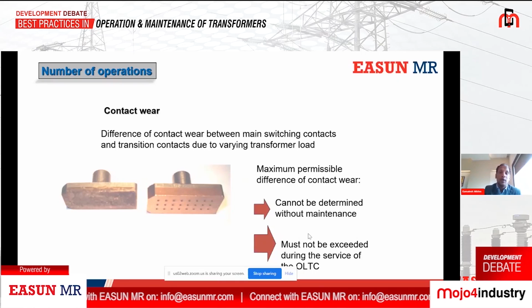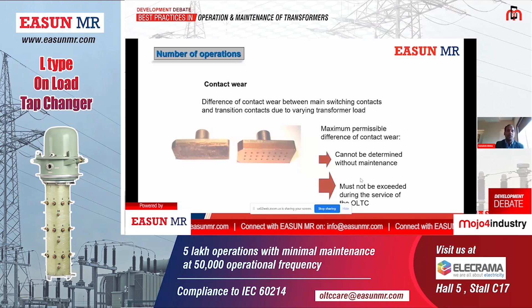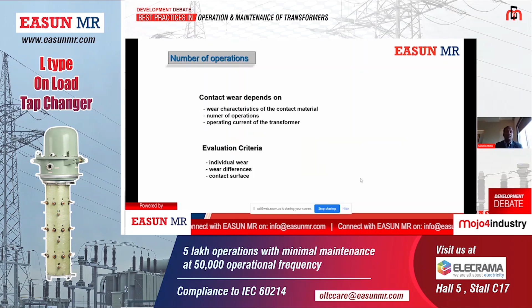And why you have to do this, as you know very well, is that since opening and closing happen within the oil, there is always arcing within the oil, there is fire, a different chemical composition happens, and slowly the contact deteriorates. This depends on the characteristics of the contact materials, the number of operations, and the operating current of the transformer. That is most important: at what current and what kV, what transformer ratings you are using at a particular time.